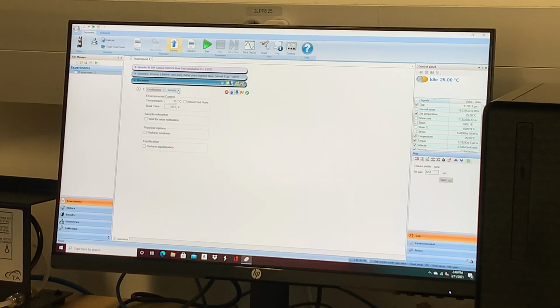So, conditioning. This is where you would do pre-test sample conditioning, like set a temperature, start a pre-shear, right? Because if you're running a fluid, when you just start the test, you'll see viscosity will be high and then it'll drop down because it's just starting. So if you do a pre-shear and then start the test, it'll be nice and smooth.